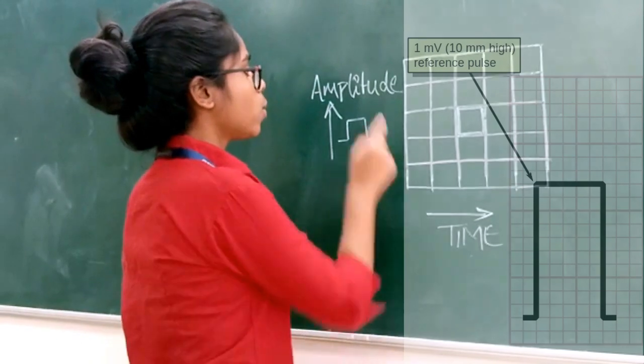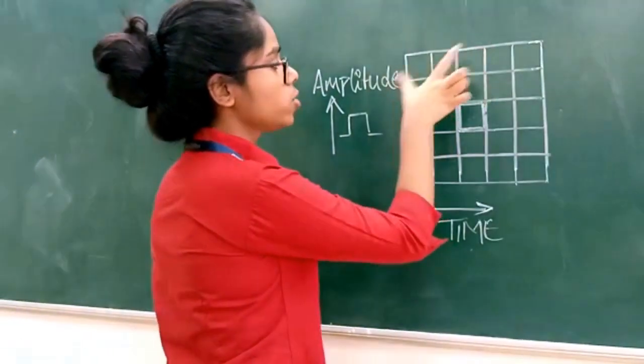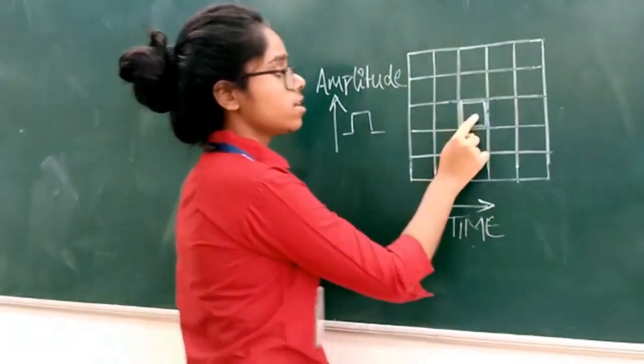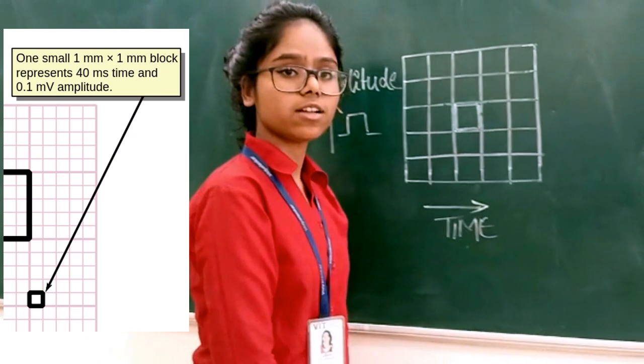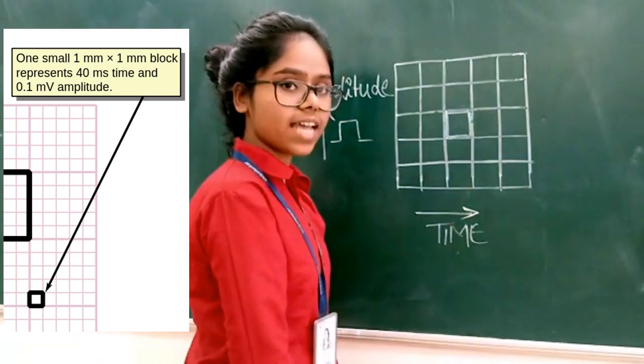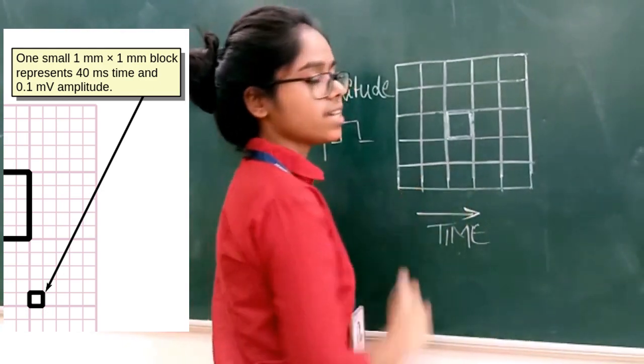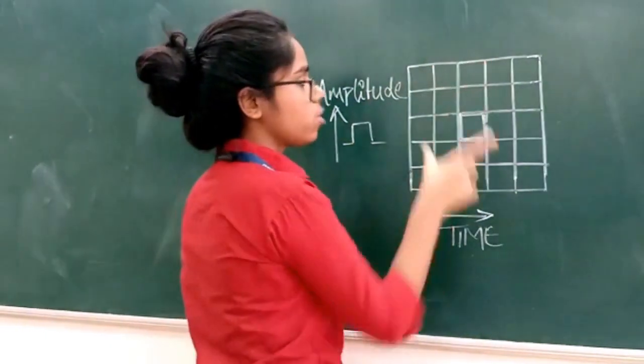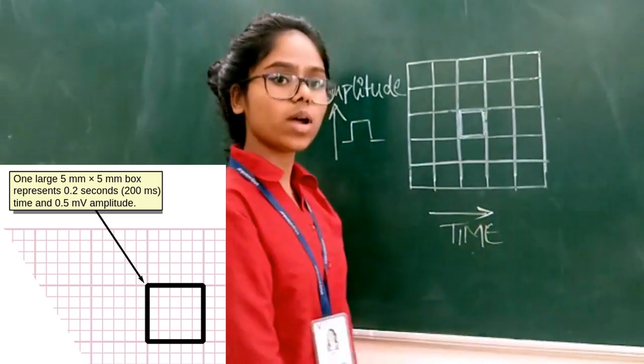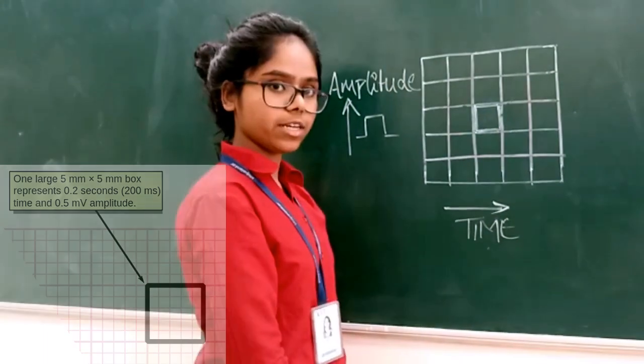It starts with 1 mV pulse calibration. You can see the big block and 25 small blocks in it. The small block is 1 mm by 1 mm, where 0.04 seconds is the time and 0.1 mV is the amplitude. The big block is 0.2 seconds, that is 200 ms, and 0.5 mV.